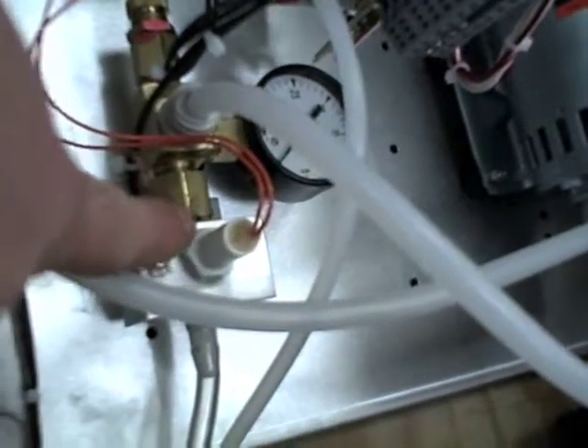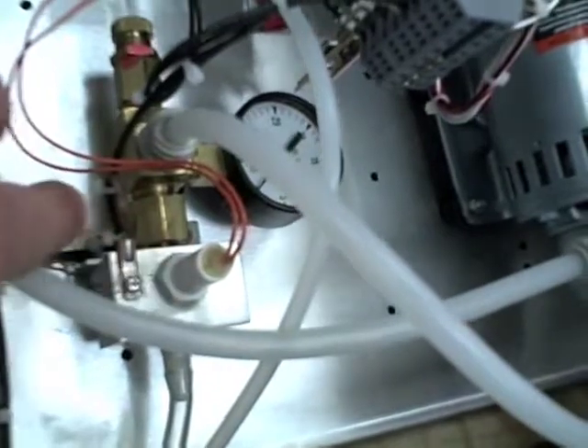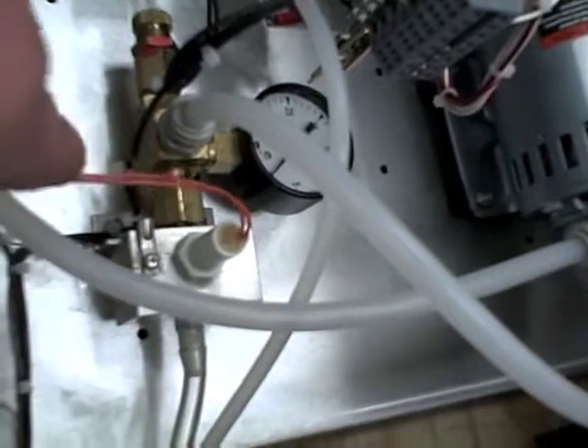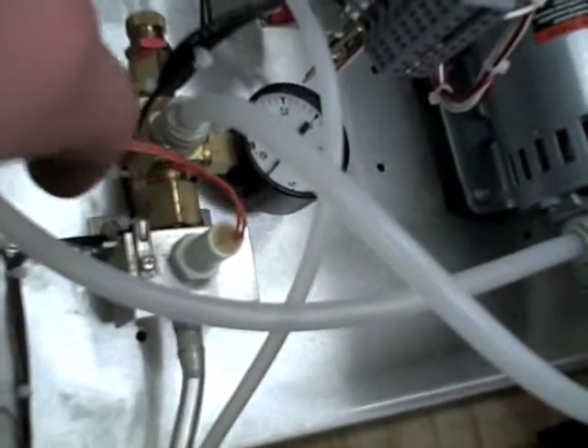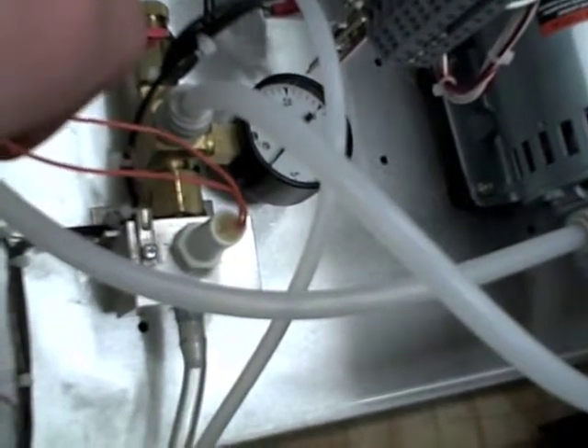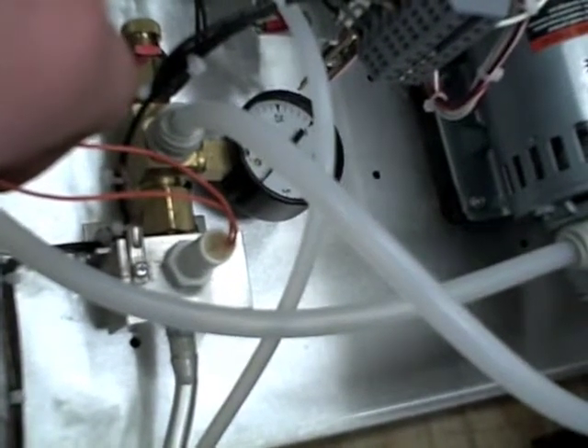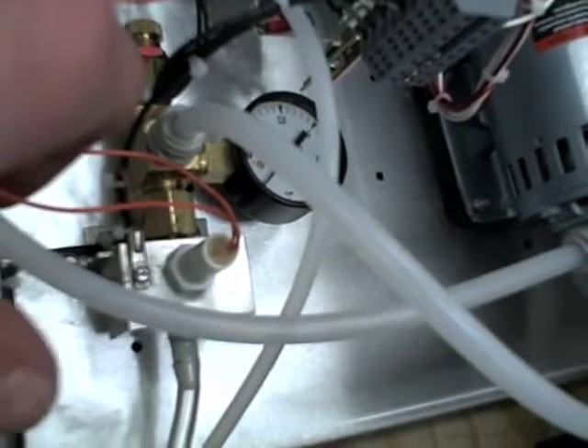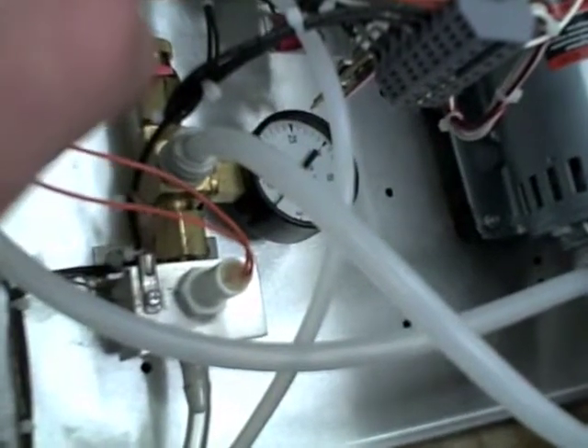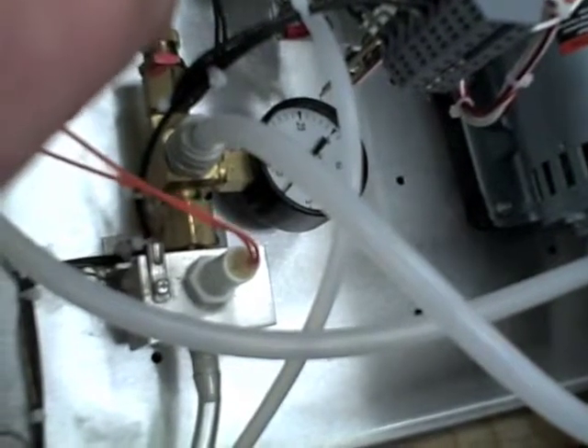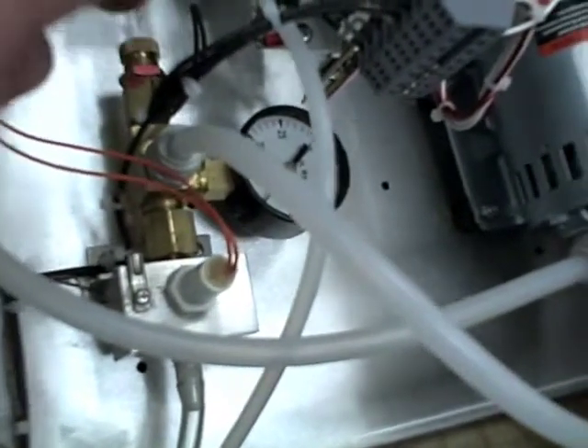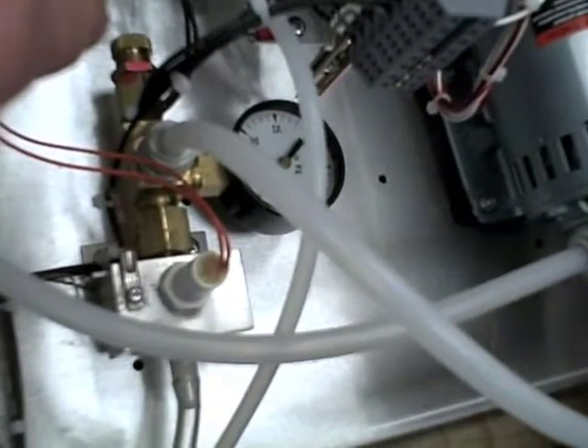Again, down here is the sensor. We've just changed the style of our sensor. You'll notice it's maybe a little taller fitting than before. Same operation as the previous model. Still orange leads, and the orange lead sensors are compatible with only certain revisions of the amplifier boards on the back of the machine. It would be 1.68.01A or K. K for krypton, A for argon.